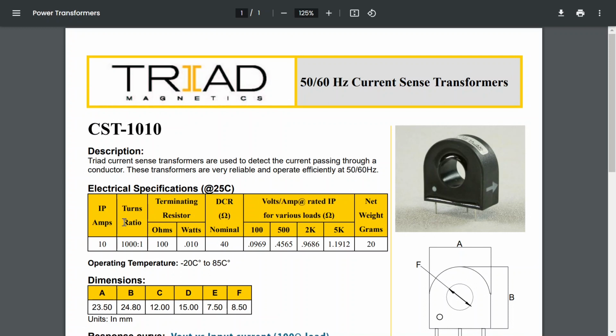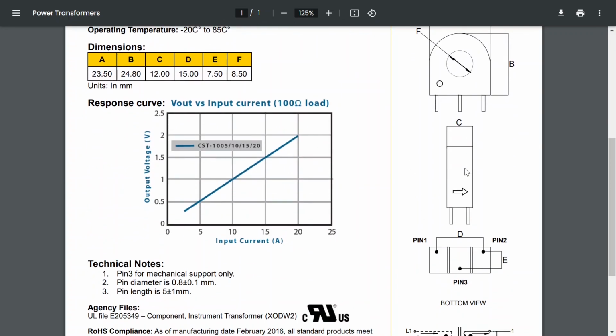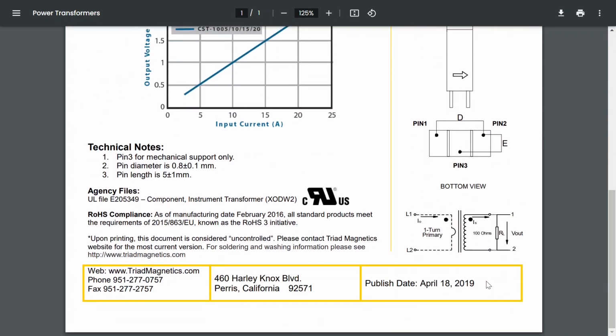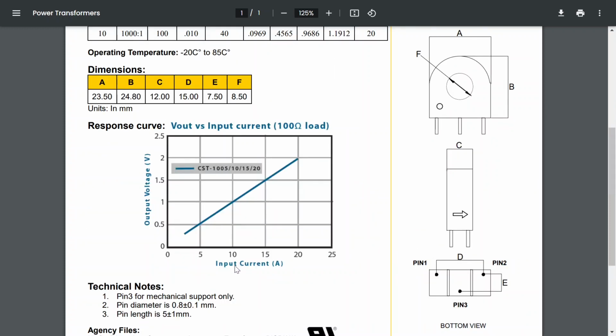It's designed to measure 10 amps, and it works very simply. All you need to do is pass a wire through the aperture of the transformer, and on the output terminals 1 and 2, it will provide a voltage. One turn through the aperture, and there's a voltage developed on the output, assuming there's a 100 ohm burden resistor as RL. Based on this chart, it looks like a 10 amp current results in a 1 volt output.